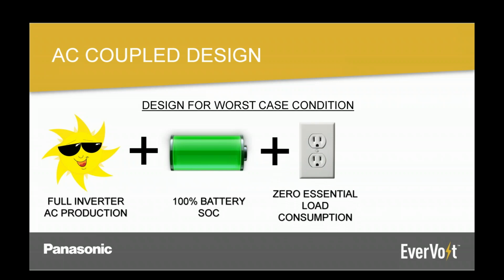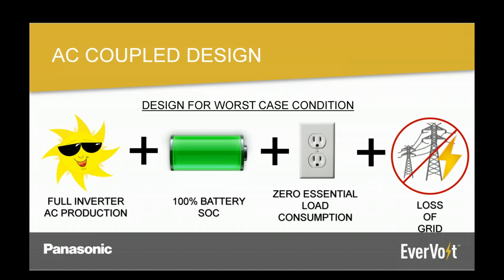What the worst case means: let's say it's the middle of summer, you've got full inverter production, your batteries are at full state of charge, topped off, the homeowner isn't running any essential loads, and the grid is out. In that case, your PV array doesn't have anywhere for that power to go, so it will simply turn off. That's the worst case you want to design for.